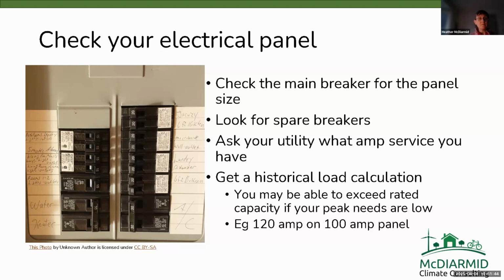If you think you're getting close to needing an upgrade, or may not have enough space, look into getting a load calculation done. You may be able to exceed the rated capacity of your panel if your peak needs are low—for example, 120 amps on a 100 amp panel.